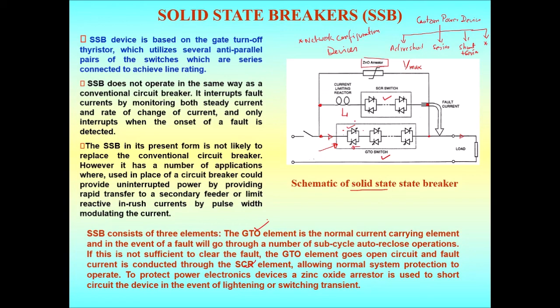Once the voltage has gone to V max in a short period, the current across this line starts increasing because there is an inductor here. For a given voltage, the current starts increasing. Once the current reaches the maximum value limited by the value of this L, then gradually these SCR switches are turned off, and slowly the current becomes zero. That's how the whole solid state circuit breaker operates. So there are three important elements: the GTO, the SCR, and the ZnO arrestor that make circuit breaker operation possible for the solid state switches.